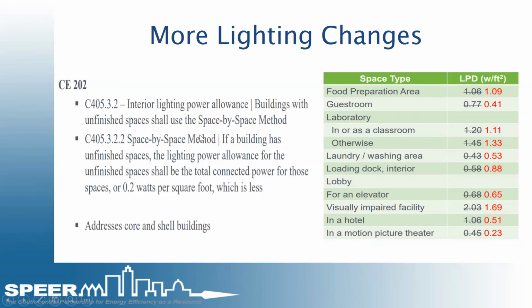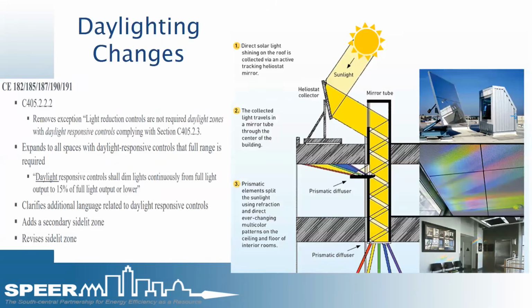Just keep in mind, if you're doing a shell, you've got to do the space by space method, not the building area method. So it breaks down core and shell buildings and adds some specifications, and modifies all the lighting power density tables - they've all been modified.